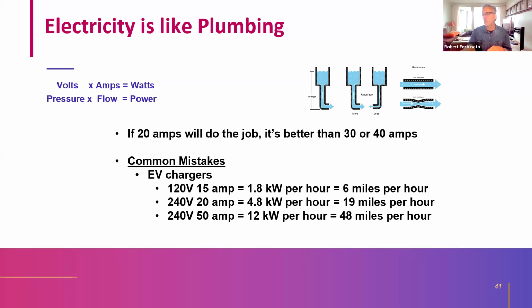If you needed more, 240 volts at 20 amps gives you 4.5 to 4.8 kilowatts per hour, or 19 miles per hour, so overnight you can get over 100 miles. Most people don't drive 100 miles a day, so it's more than enough. If you needed even more, a 40 or 50 amp breaker gives you 12 kilowatts per hour, or 48 miles per hour. But thinking about these things, we realize most people will never use what a 50 amp breaker gives them, so it's unnecessary. We wanted to illuminate that so people have more opportunity to use what they have, rather than doing expensive upgrades that aren't needed.